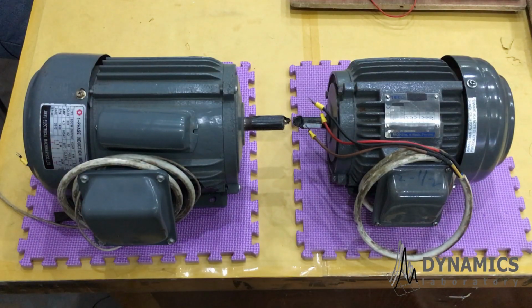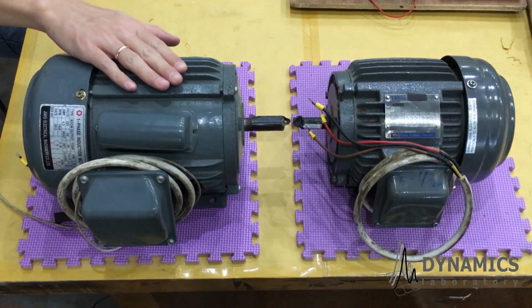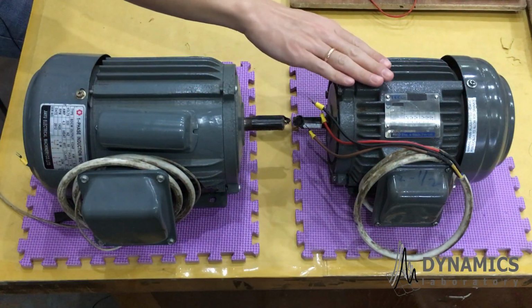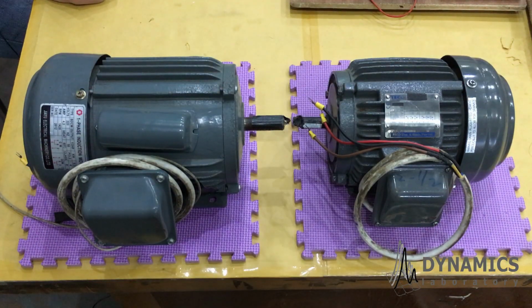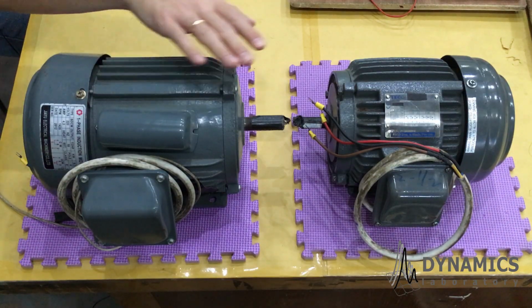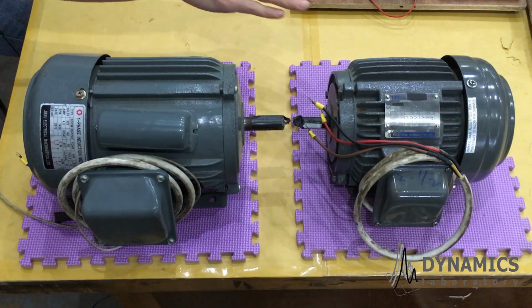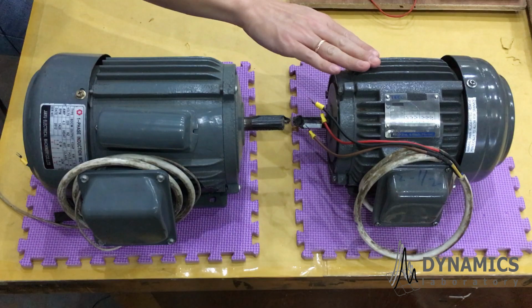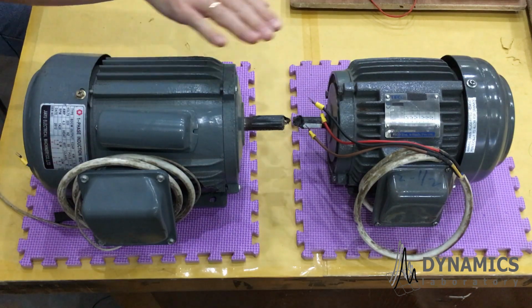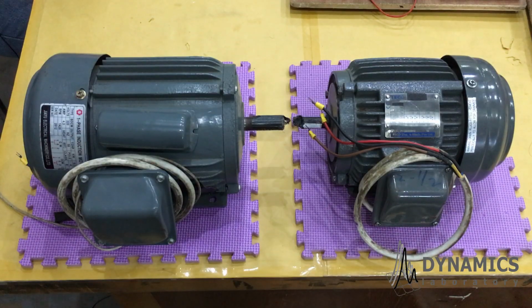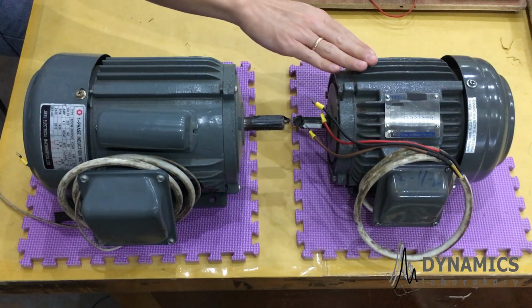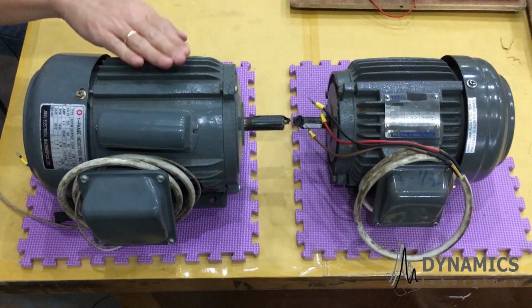Before we start the experiment, I want to show you the one-phase and three-phase AC motor. This is the one-phase AC motor, and this one is the three-phase AC motor. Based on appearance, how do you differentiate one-phase and three-phase AC motors? First, look at the size. If both motors have the same power, then the three-phase AC motor must be smaller than the one-phase AC motor. Both of these motors have an output power of 0.5 horsepower. That's why you can see here, the three-phase AC motor has a smaller size than the one-phase AC motor.